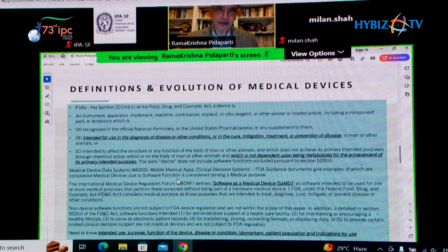The same is expanded to AI/ML, which is artificial intelligence, and software as a medical device. FDA published a position paper, and this is content from that, where they basically say artificial intelligence has various aspects. Generative AI is artificial intelligence, and machine learning is artificial intelligence. And they can be locked or unlocked medical devices. Machine learning can be locked, meaning it doesn't change the output for the same input. If it is unlocked, that means the machine is learning, and for the same input you may get a different output. The reason for all this is that these things have to be thought through when you're designing a medical device, and then you have to provide documents to the FDA or any regulatory agency you're submitting to.